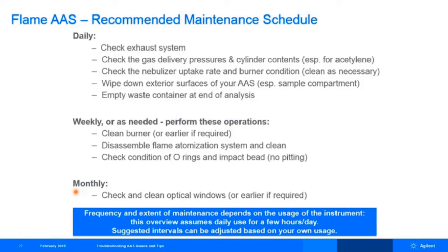Again, periodically, perhaps monthly, we want to check the optical windows on the instrument and clean them if necessary. So if you follow those procedures, then you should be able to achieve good and consistent performance from your instrumentation.